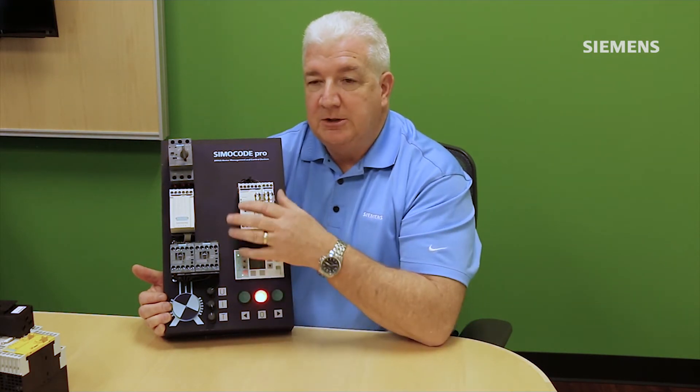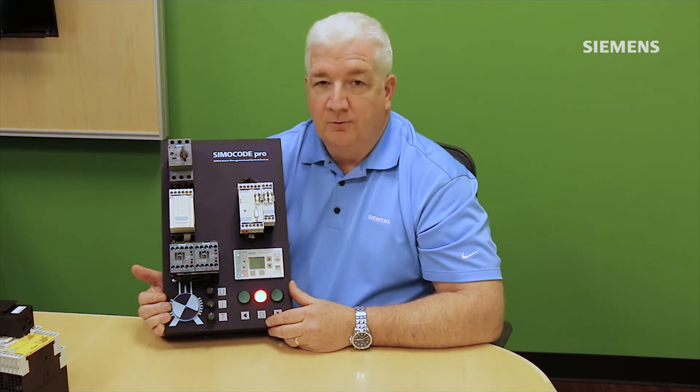The response to fault conditions can also be customized with SIMOCODE. With a traditional overload relay, the only response when an overload is detected is to shut the motor off. With SIMOCODE, you can modify the response so it doesn't necessarily shut off the machine right away. There may be other control functions — like closing a valve — you want to perform first. SIMOCODE can detect the overload condition, allow the machine to execute those other functions, and then shut the motor off.